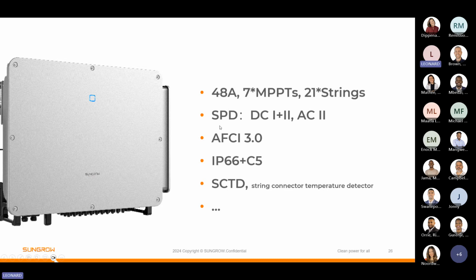This will also have SPD protection built into it, with DC protection class 1 and class 2, and AC protection class 2. It will have our new arc fault circuit interruption 3.0, which will be a completely fuseless design as well. And it will be IP65 or IP66 plus C5 aluminum enclosed.